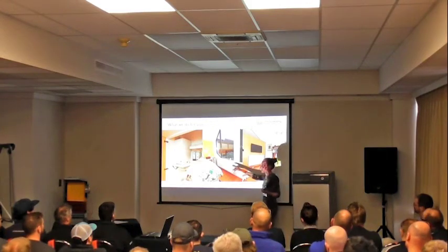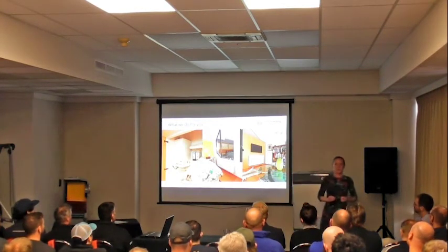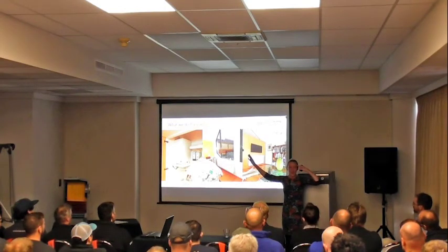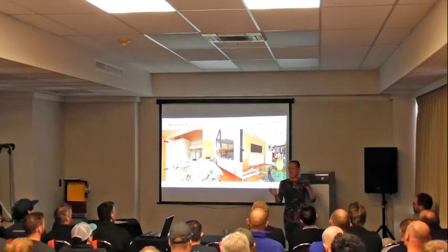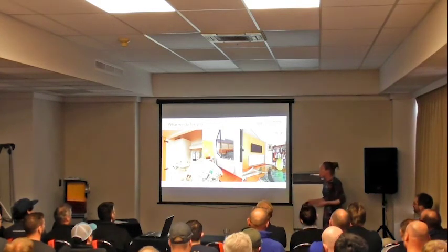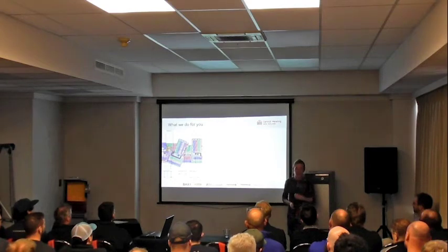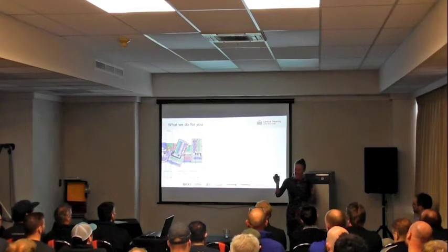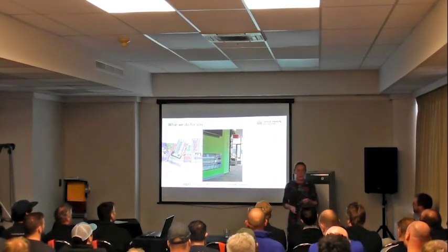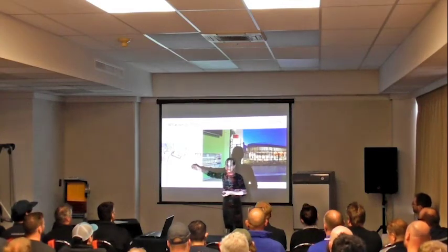We take all the headaches and responsibility out of it by actually designing the system. Why I show this picture in particular — this got Canterbury House of the Year, it's down close to Sumner. The customer was German, very used to gas boilers — that was literally what he was born with. He was a marine engineer, absolutely only knew radiators and gas boilers, old school, and absolutely wanted a boiler. Now we all know what a gas boiler running on LPG costs — you're so lucky on the North Island that way. But we gave him exactly what he wanted. What we do in the engineering side is carry out a heat loss on the property and determine what kilowatt output is required for each of the emitters in each room, then add it all up for the heat source. What we give back is a pretty layout for the homeowner, a quotation, and as you work through installation we'll supply a pipework layout or an underfloor layout.